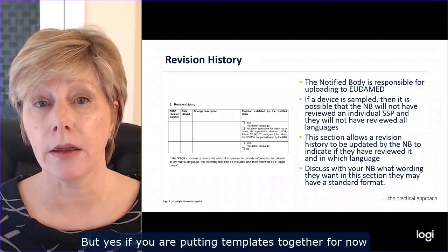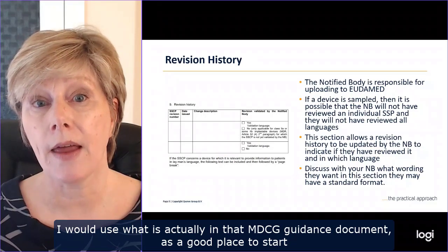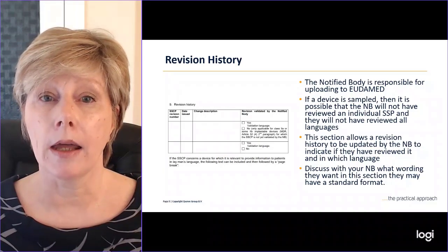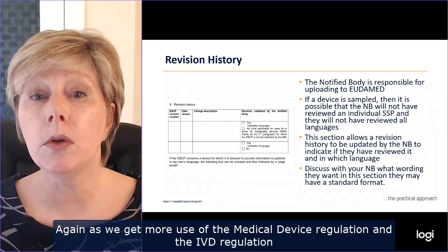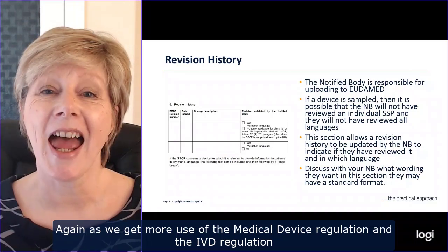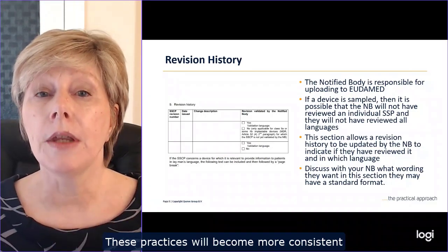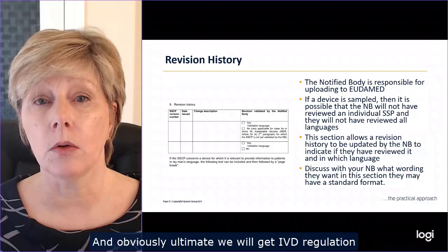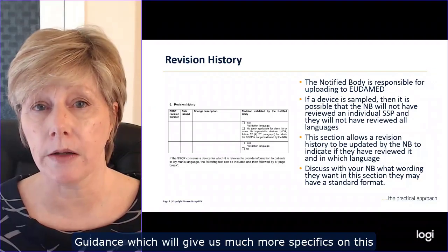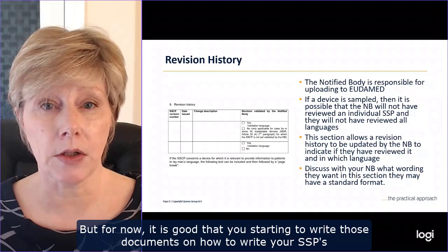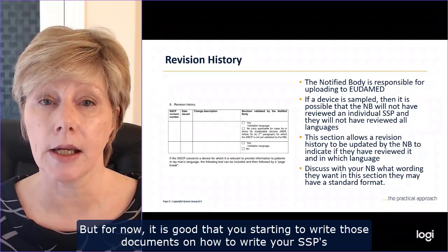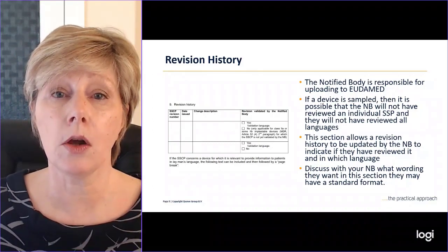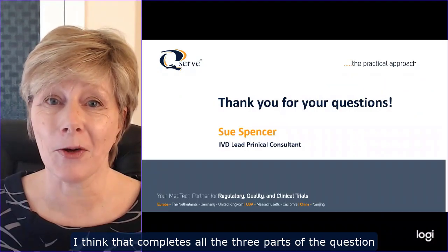But yes, if you're putting templates together for now, I would use what is actually in that MDCG guidance document as a good place to start. And again, as we get more use of the medical device regulation and the IVD regulation, these practices will become more consistent, and obviously ultimately we'll get IVD regulation guidance, which will give us much more specifics on this. But for now, it's good that you're starting to write those documents on how to write your SSPs, but it would be a good thing, I would say, to put in your templates. So I think that completes all the 3 parts of the question.